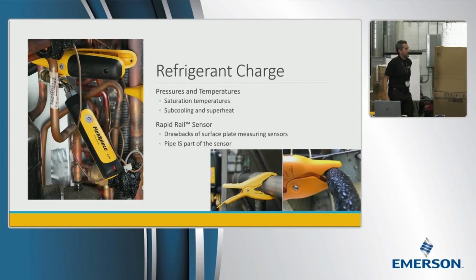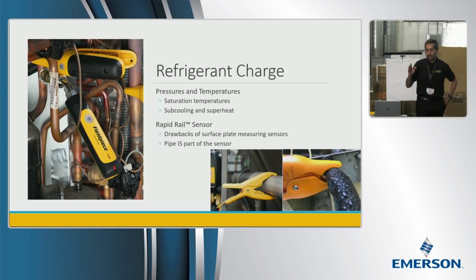Let's talk a little bit about refrigerant charge. In essence, the main way that we measure refrigerant charge is, we all know, subcooling and superheat, right? Based on the metering device that we have, one measurement tells us more about the refrigerant charge. The reason that we're taking pressures on a system is to get saturation temperatures, and then saturation temperatures get compared to pipe temperatures to give us those subcooling and superheat values. Now, when we're talking about location and timing of pressure measurements, for location, we don't have too many options. We have service ports, and that's pretty much going to dictate where we measure high side pressure and low side pressure.